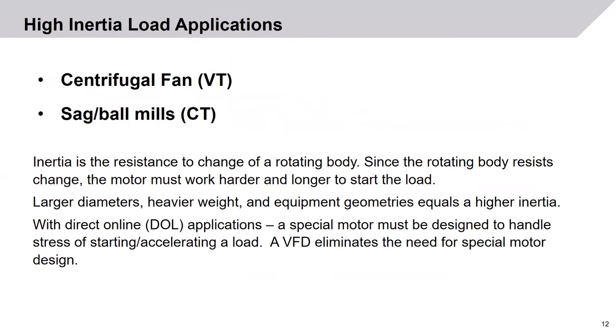High inertia load applications: some applications have inertia problems, such as centrifugal fans or sag/ball mills. Centrifugal fans are variable torque and mills are constant torque, so torque profile is not the primary concern here. Inertia is the resistance to change of a rotating body. Since the rotating body resists change, the motor must work harder and longer to start the load. Larger diameters, heavier weight, and certain geometries result in higher inertia. With direct online (DOL) applications, a special motor must be designed to handle the stress of starting such a load. VFDs, however, will eliminate the need for special motor designs.